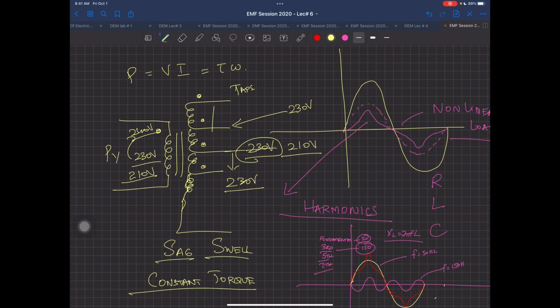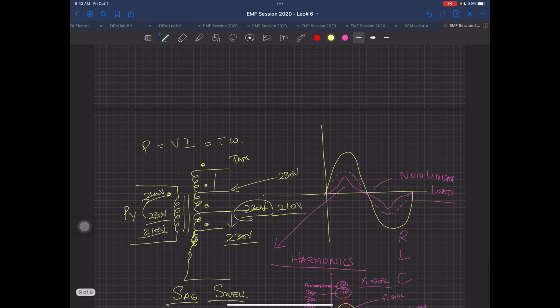And all this is because there is a pressure of the gas, and that creates a constant torque load. Like this fan running right now, it's blowing air. If I increase the air pressure in this room, the fan blades will have to work harder. The same thing happens inside the fridge. The load is constant. If you decrease the voltage, the current will increase because the power stays constant. So when power is constant, you get that problem in your fan or fridge, and the compressor will be burned down.